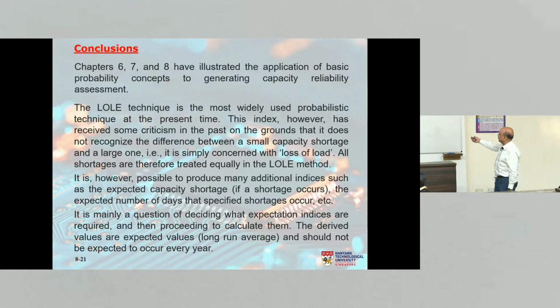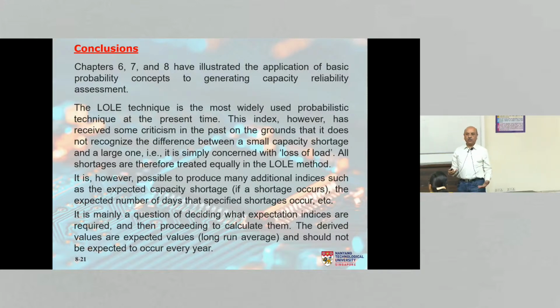It is, however, possible to produce many additional indices. While we have focused on only two indices, LOLE and LOEE, no reason why you can't look at other indices. If you are interested in expected capacity shortage, you can define that as your risk and therefore use the capacity outage probability table and calculate the risk of capacity shortfall. Or you can use the expected number of days when specified shortages occur as your risk index. So there are many risk indices you can create for your own system, but the probabilistic way of dealing with them will be the same, just the two indices that we have seen. The calculations will be very similar.